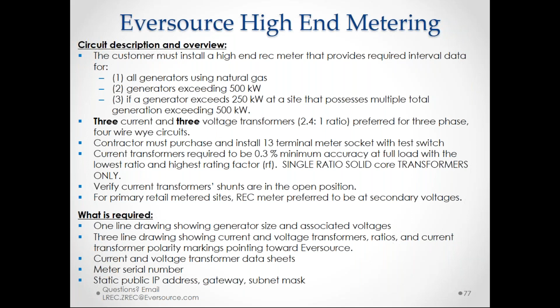So it's going to essentially get the most bang for your buck on that REC design, and it's also going to increase the chances that the amperage will be lower, and therefore you'll have the opportunity to put in one of those self-contained options. If you put it on the 208 volt side of the customer transformer, chances are your amperage is going to be higher, and now you have to go to the more complicated 9S CT-rated configuration, where you're purchasing those CTs and having to show more detail. So it's just better for everybody if you keep it on that higher side closer to the generator, where there's more likelihood you can go with a self-contained option.